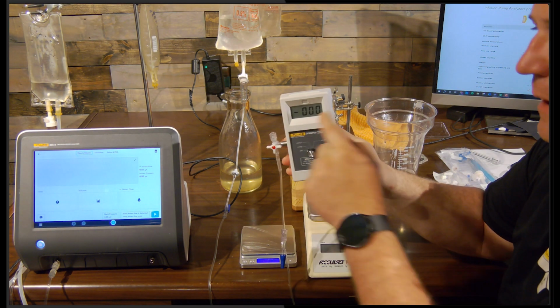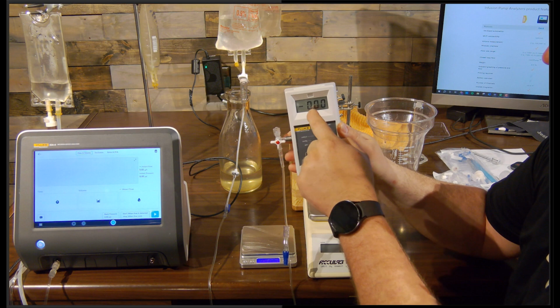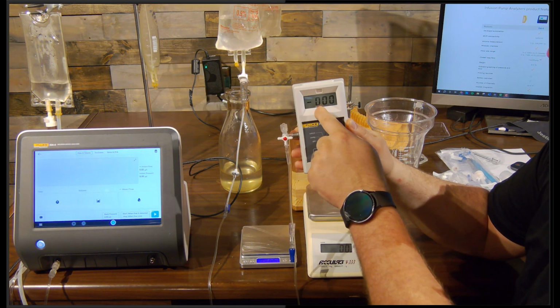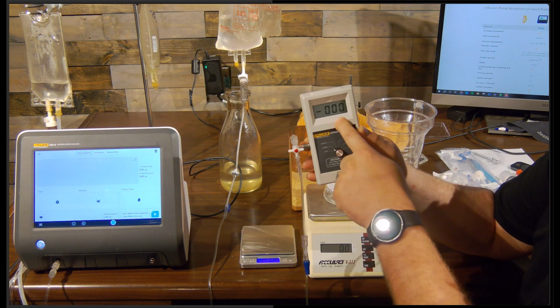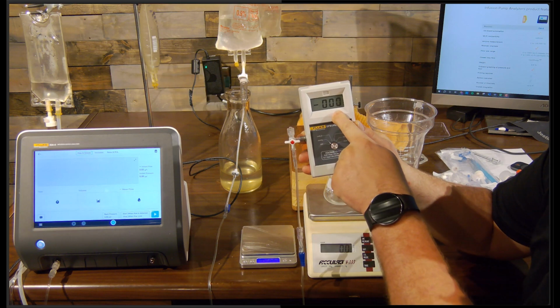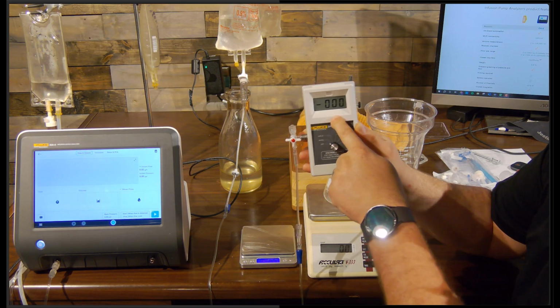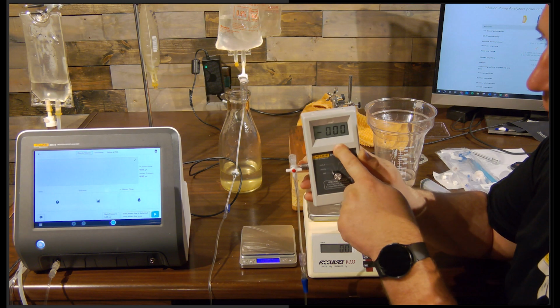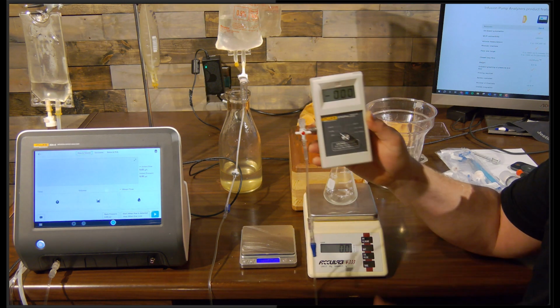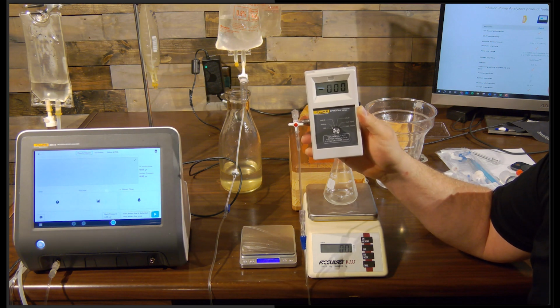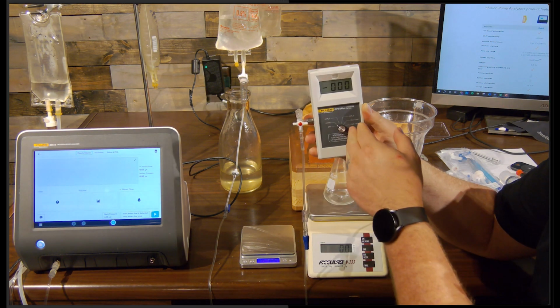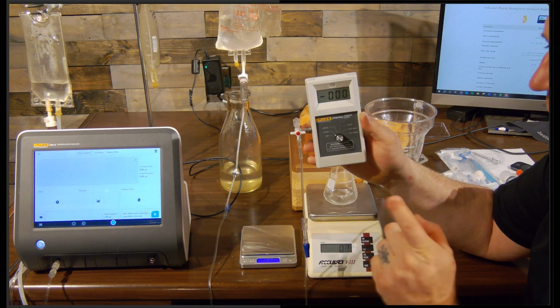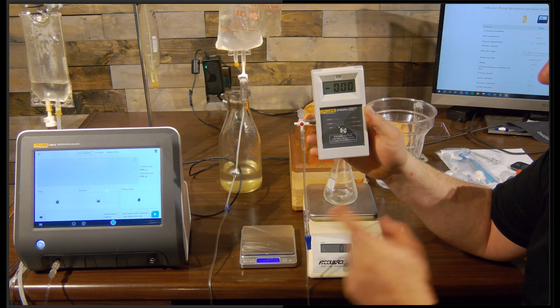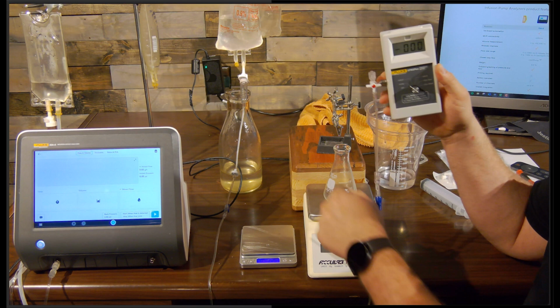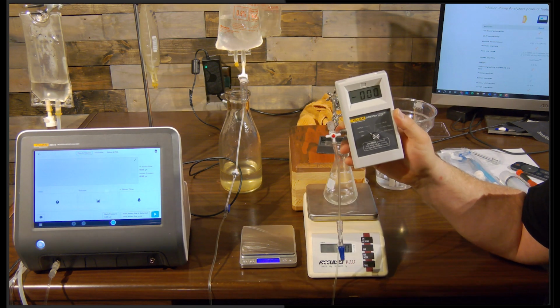But again, I need to be here and paying attention when my infusion pump alarms to get the peak pressure, because some infusion pumps will start to back that pressure off, and I won't actually catch the peak. I'll catch something after the peak. And again, how far after? So will your pressure meter catch the peak pressure? Or do you have to be sitting there and paying attention? And I'm telling you, the human error thing really starts taking effect when you have 2 or 3 possibilities of human error here and a few possibilities of human error here.